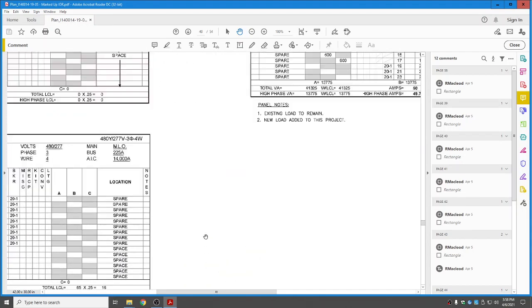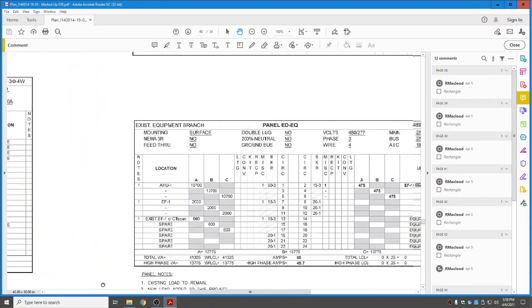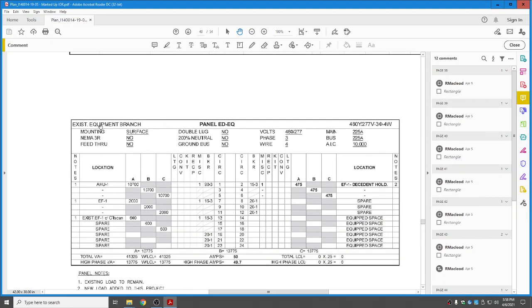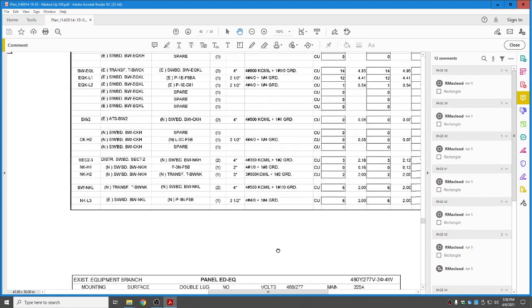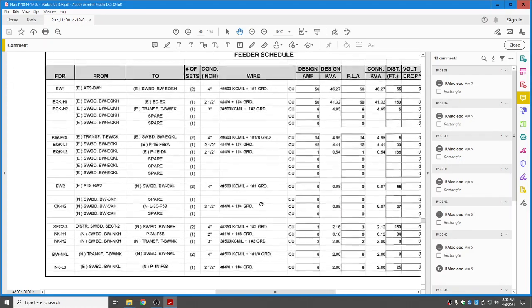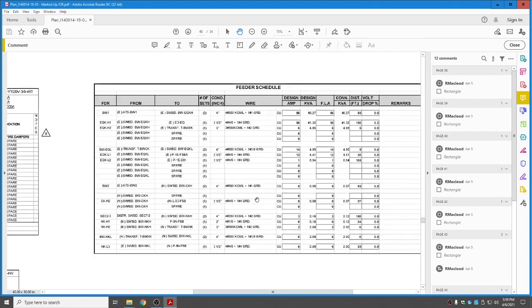Okay, let's jump up. Here is an existing equipment branch power panel. You see the EQ for equipment branch, and it's 480, 277. And here's a very important item that sometimes people can't find on the plans. Let's talk about this. This is the feeder schedule. This is going to tell us the size of the conduit and the wiring inside that conduit that go from, for instance, switchgear to panel board, etc.